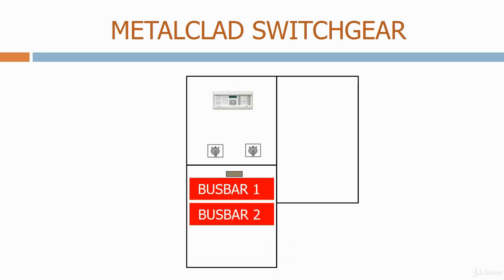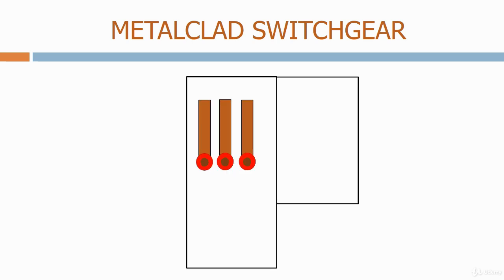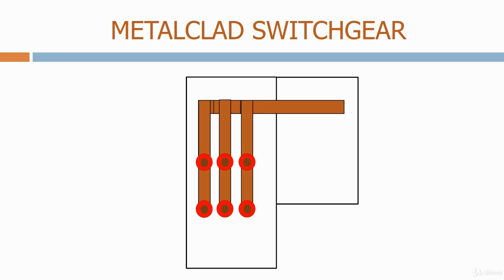The first thing you notice is that both of the circuit breaker shutters are red. This is because we're connecting two bus bars together, and as you would expect, one is labelled bus bar 1 and the other one bus bar 2. In the bus bar chamber, we have the bus bars coming from bus bar 1 on the left, going down through the circuit breaker, and back up through the bus section riser chamber to bus bar 2.